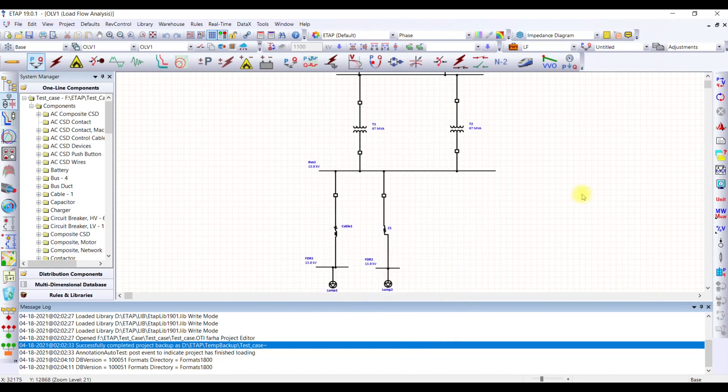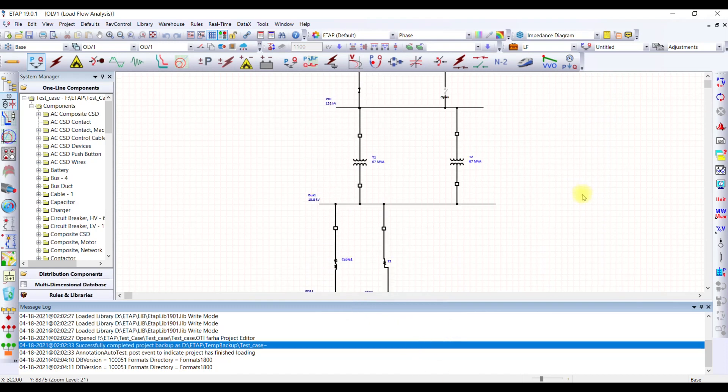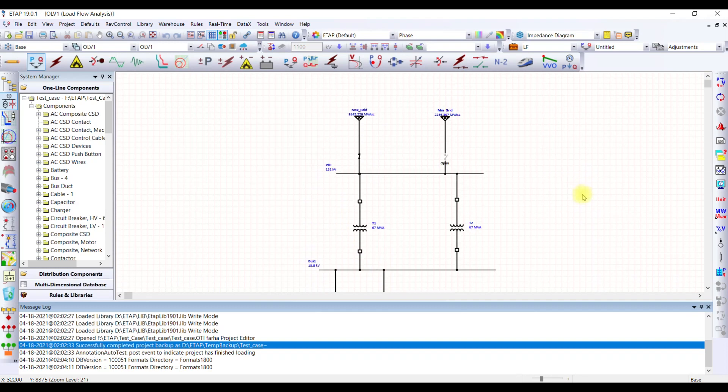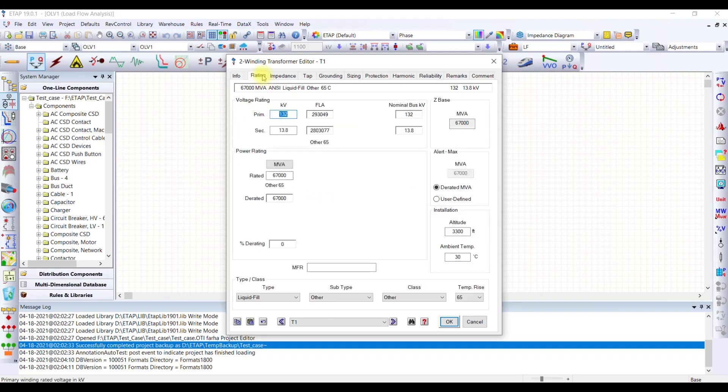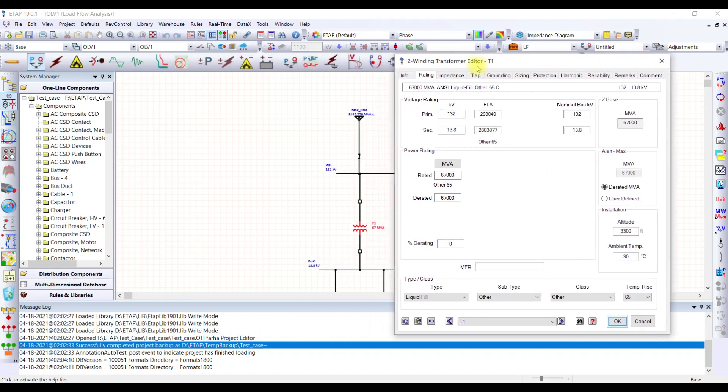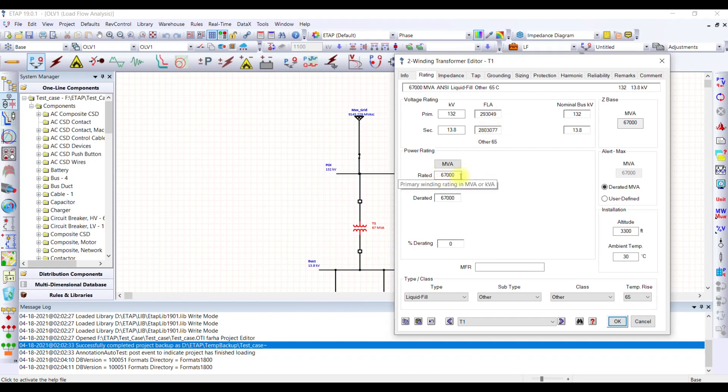This is how you open the case and perform analysis. If you want to check the data of something or manipulate the data, you simply have to double click on the equipment and the window for that particular equipment will open. If you see here, the ID is transformer T1. If I go to the rating, the voltage rating is 132 by 13.8 kV transformer which has a huge capacity here, 67 MVA.